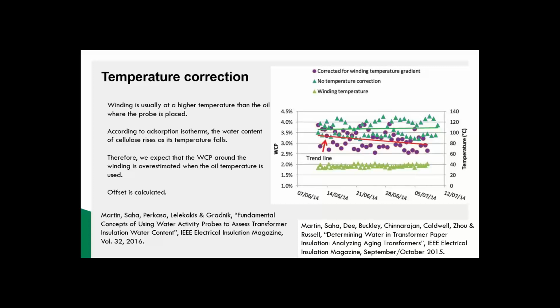Now the importance sometimes is, well, the utilities generally have different limits of what they consider as when they have to take action. Sometimes it might be around 4% where the utility starts to think about drying out a transformer. But actually, if we apply this algorithm and we come down by 0.5%, then that might just mean they don't have to perform the operation yet. So maybe they can save themselves some money there.